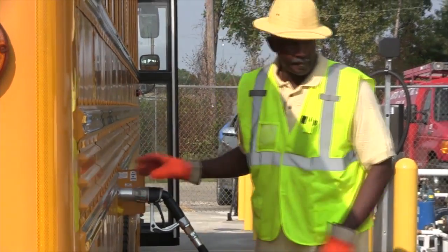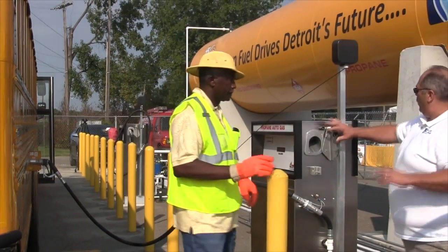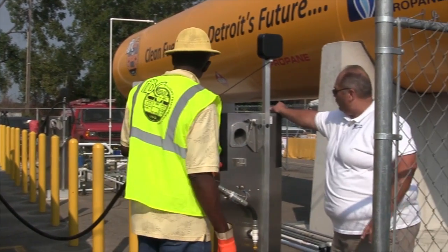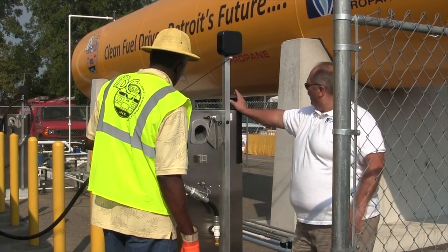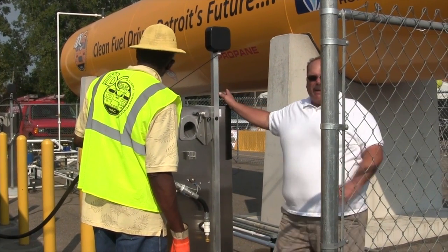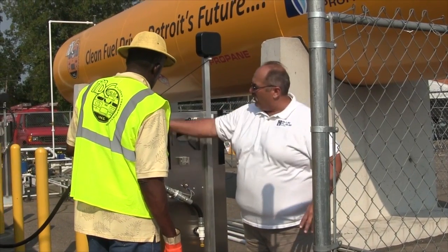He's going to come over here and turn this on. This right here actually turns one of those blue boxes, which is an electronic shut-off valve. It's got a solenoid which shuts the gas off. He turns that on, it's going to open up that valve. There's going to be a 30-second wait for safety, then the gas is going to come through.